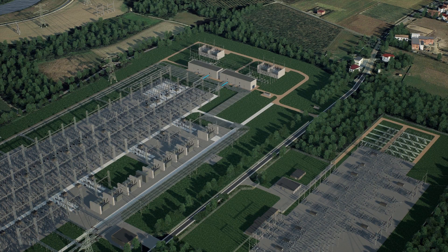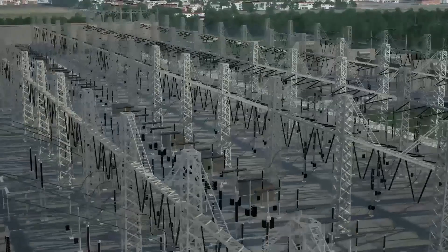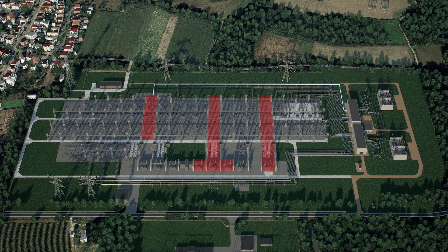The switch to the new substation requires a link with the old substation. The first step in the takeover process is the commissioning of two new power transformers. This way, two bays at the 150 kV substation are freed up for renovation. To realize the transfer, the conductor to the old substation is disconnected and subsequently reconnected to the new GIL connections. One by one, the existing connections can be taken over.